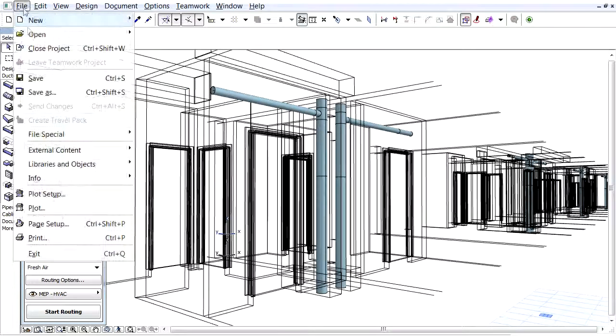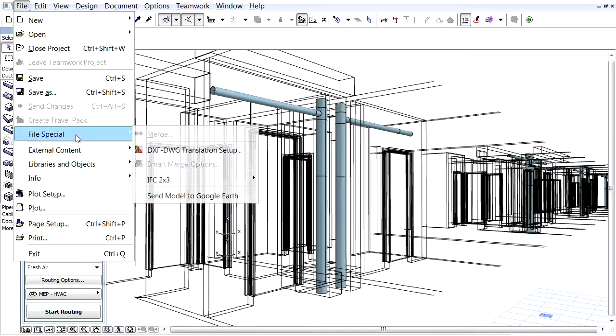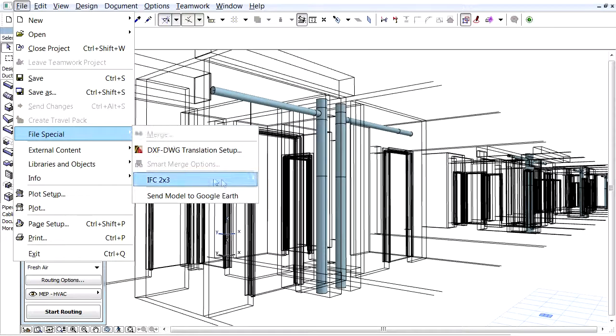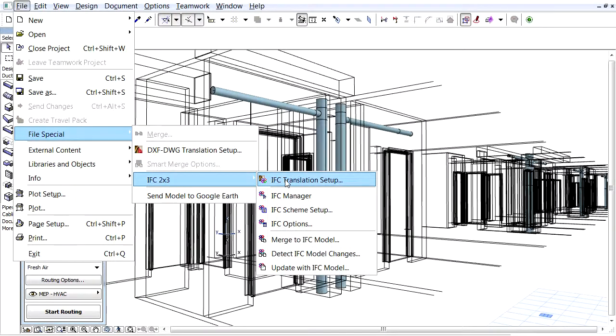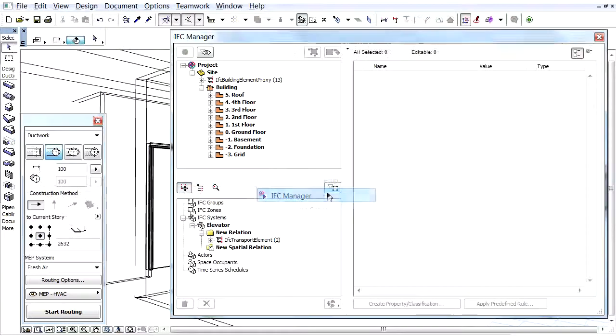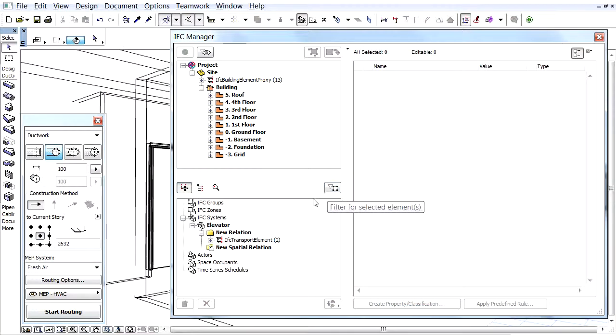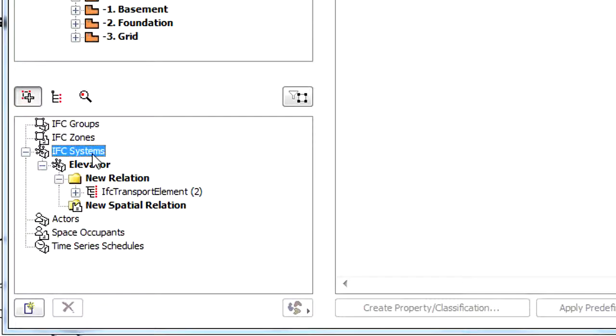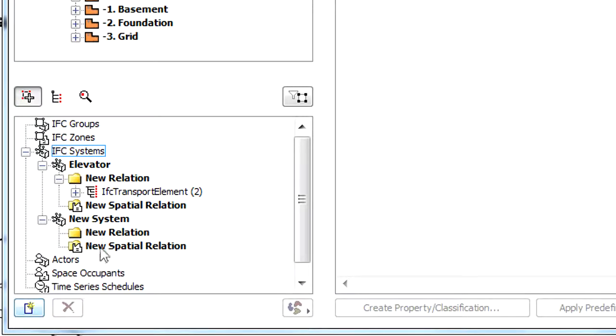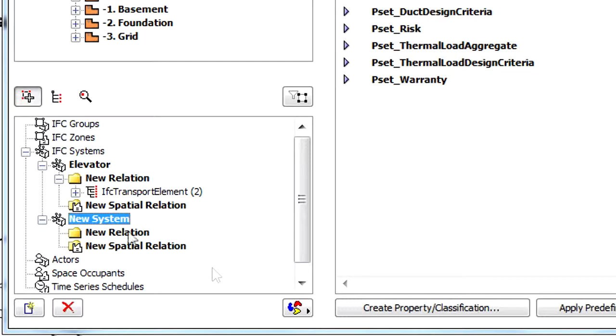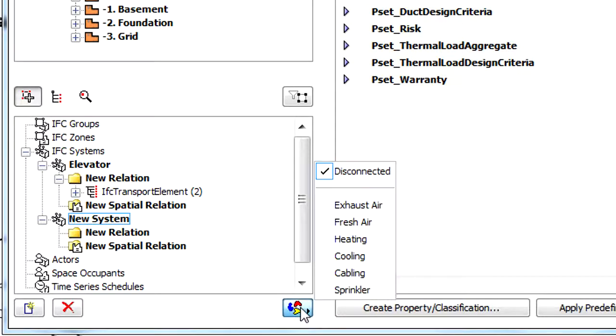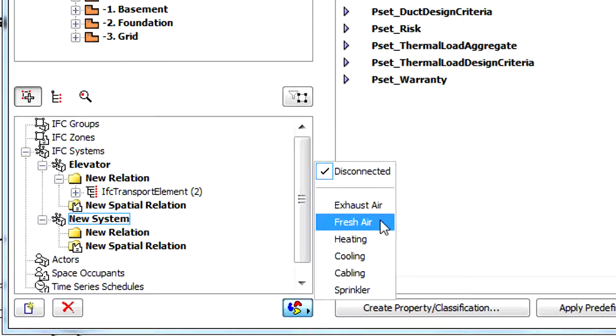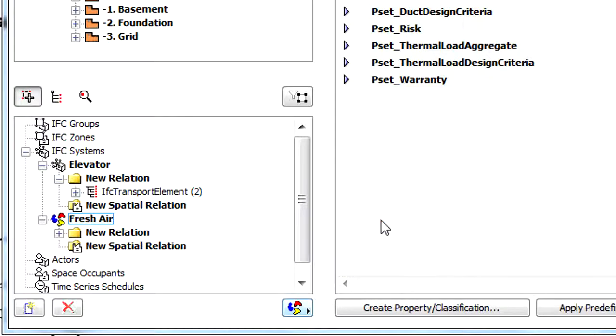The 3D view shows some pipe members of the Fresh Air system defined by the Graphisoft MEP modeler. By using the IFC Manager again, you can easily convert the Fresh Air system to an IFC system assignment. Just create a new IFC system in the Assignments tree and choose the Fresh Air item from the list which contains the predefined MEP modeler systems. The program automatically renames the new system to Fresh Air and assigns all members of the Fresh Air MEP system to the IFC system.